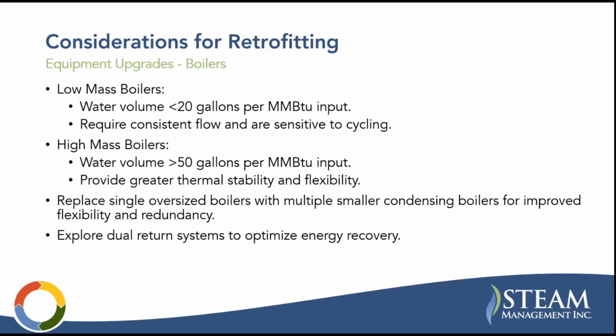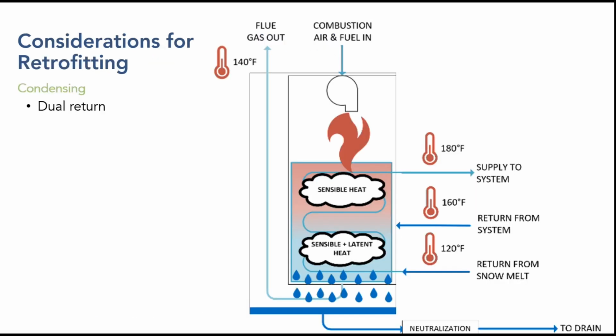You also want to replace single oversized boilers with multiple smaller boilers. I already mentioned that, but it improves your flexibility and redundancy. And you might want to explore dual return systems to optimize energy recovery and promote condensing in your flue gas. When I'm talking about dual return, this is the idea. Maybe your hot water system needs a 180-degree supply temperature and has a 160-degree return, but maybe you have some other process, like a snow melt system or a pool heating system, that is consistently returning colder water back to the boiler. And so even when you're not in the shoulder months of the heating season, you may be able to promote the boiler operating in condensing mode. So basically you have two returns to your boiler. You pick a lower temperature return to go towards the outlet of your boiler to promote condensing in the flue gas.